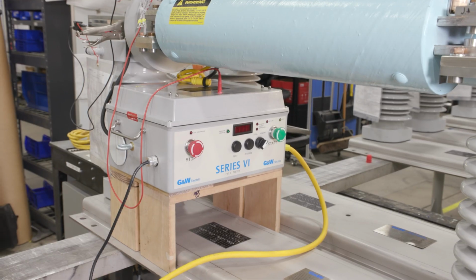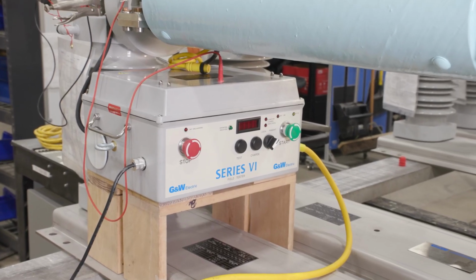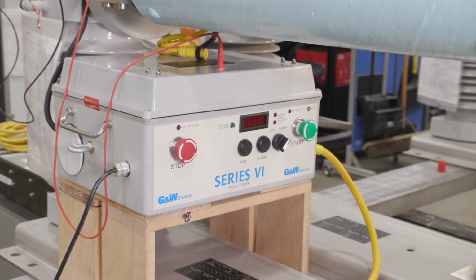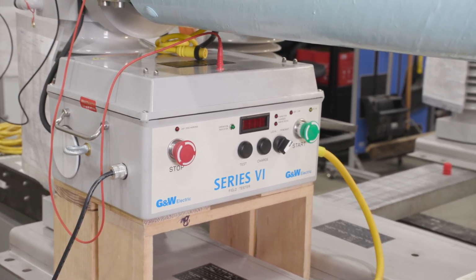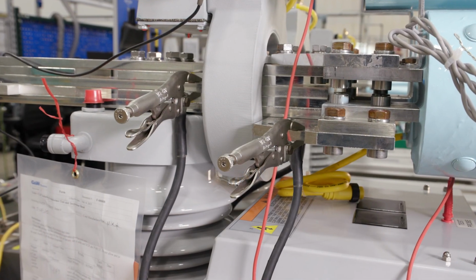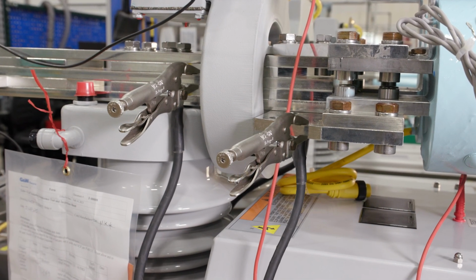Next, disconnect the shorted firing leads from the terminals on the SFL. Mount the field tester as close as possible to the SFL, with one vice grip located on each side, and clamp it to the bus using jaw-locking pliers.